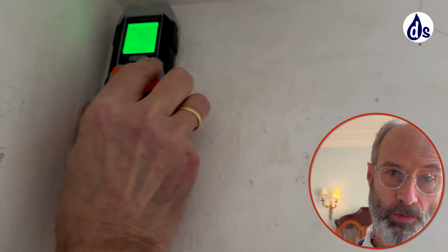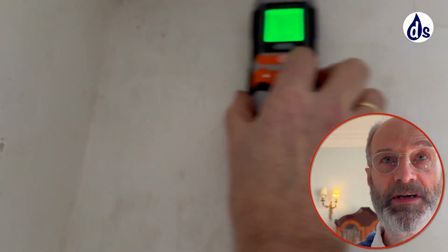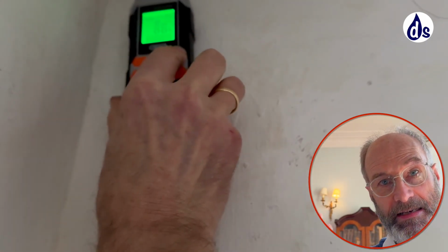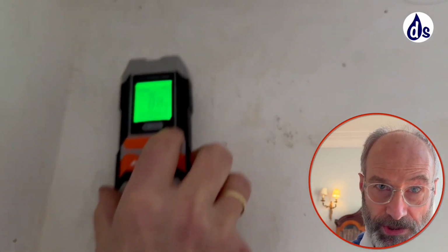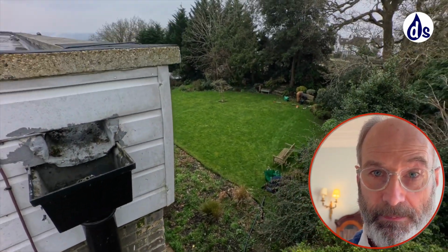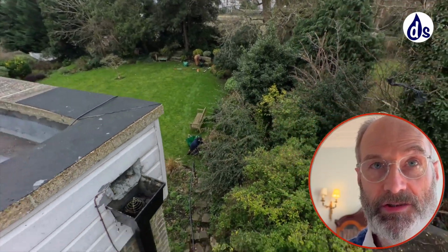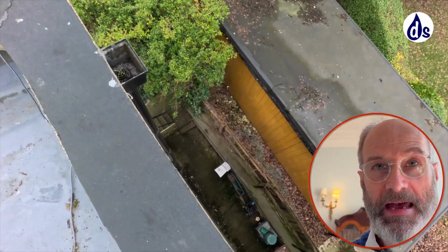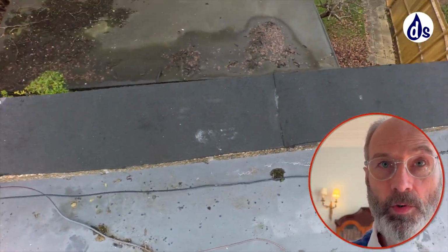So going into flat 10, we got dampness on the wall there. Actually on the outside is a hopper, and I'd already seen it from before that, but there's a light brown staining indicating penetrating damp, because the water comes through a wall, it will bring colour with it from the brick. I'm using a very inexpensive damp meter, which I encourage anyone to buy. They cost about £23. It's called Dr. Meter, and it's a way of telling whether the wall is drying.